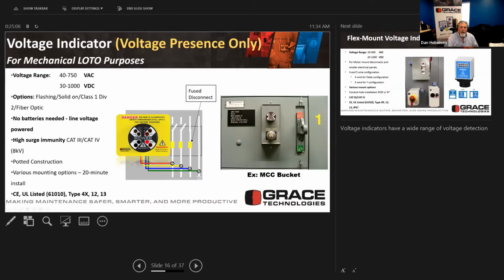If we were to open up L2, now you'll see you're in a single phase environment. A couple of things could cause the single phase environment. It could have been you had just thrown the disconnect, and 2 of those 3 blades released. Another potential problem is a thunderstorm comes rolling through and the energy provider has lost a couple of legs on their system and they're providing a single phase. And really this gives you the visual opportunity to determine what is your procedure from here in this abnormal condition. And you can react accordingly.